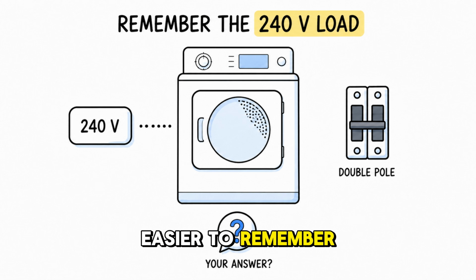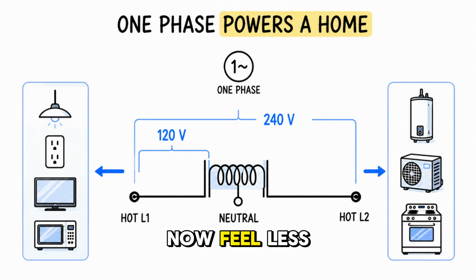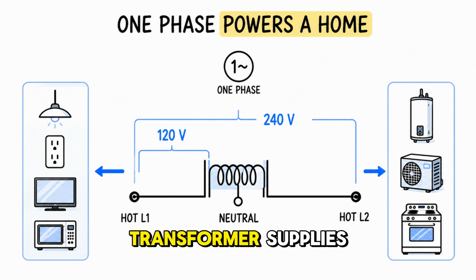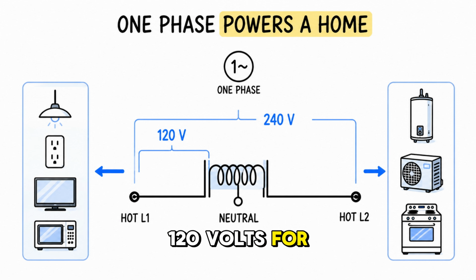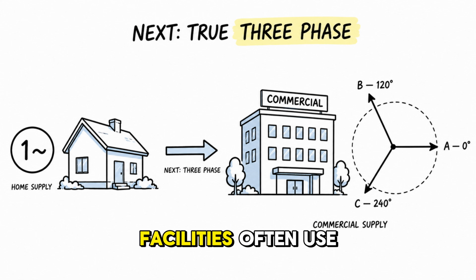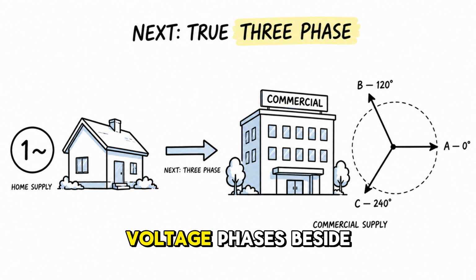Single-phase power should now feel less limited than its name suggests. It can operate an entire home, because the center-tapped transformer supplies 120 volts for ordinary circuits, and 240 volts for larger loads. To understand why commercial facilities often use something different, we need to place three true voltage phases beside one another.